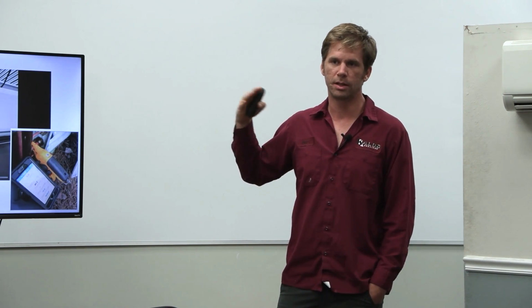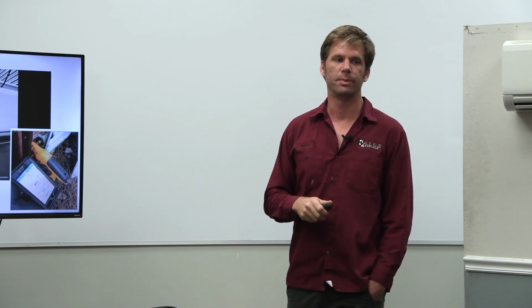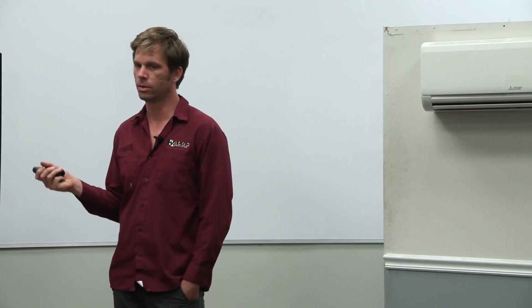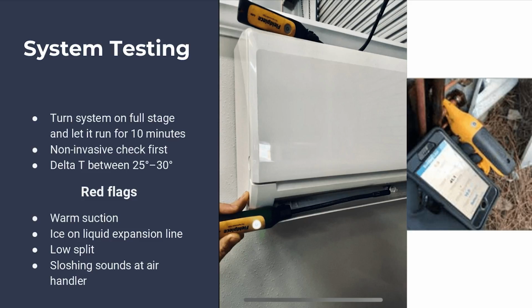But if you've got a ductless running full speed and you've got a 20-degree split, you have a problem with your charge. Something's actually going on. It should be closer to 27 degrees when you split. So you don't necessarily just have a problem with your charge. It could be other things as well.